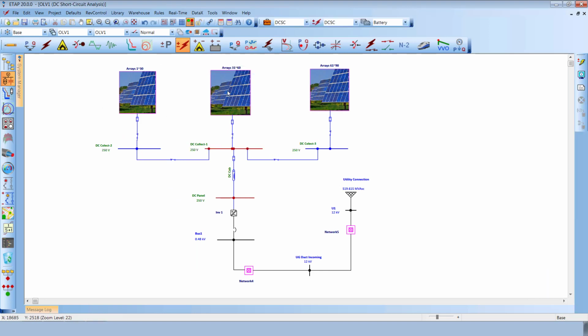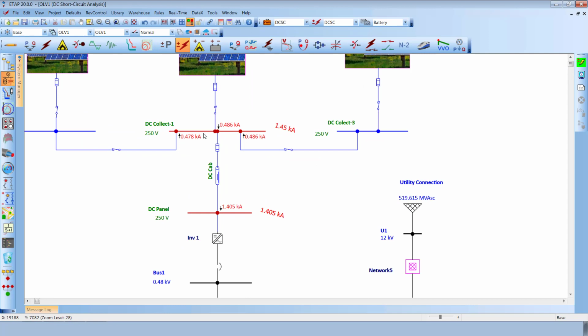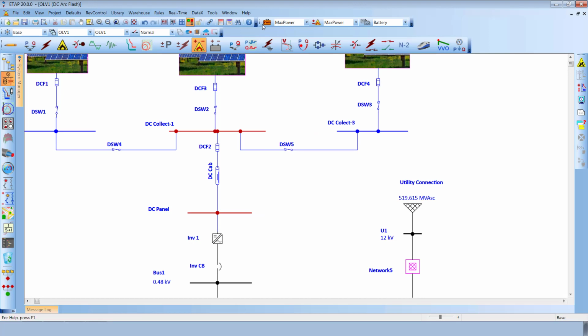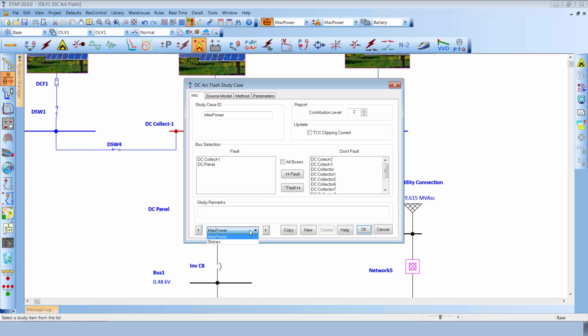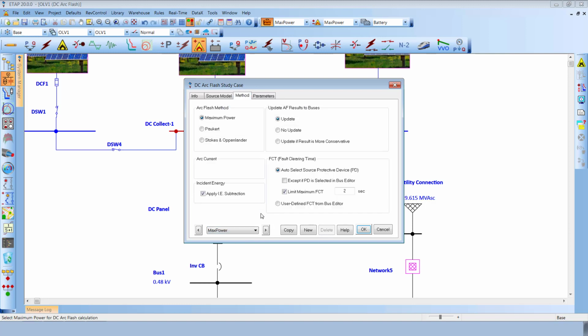Now that we entered the required data to perform the analysis, it's time to switch to the DC short circuit mode and run the corresponding short circuit analysis for the combiner box and the DC panel respectively. And this magnitude of the current is calculated based on all the PV arrays combined and fed into the combiner box and the inverter cabinet on the DC side of the inverter. Now, it is time for us to switch to the DC arc flash mode and establish the two separate study cases, with each study case referring to the maximum power method and the Stokes method respectively.